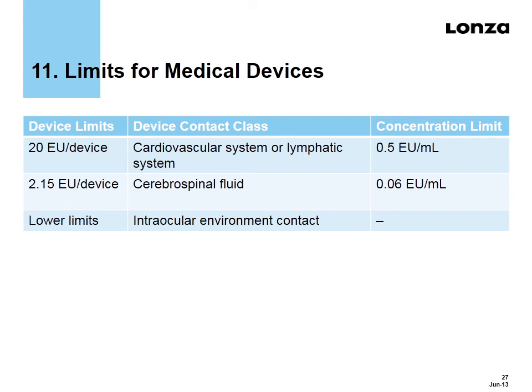Intraocular devices is a new category stemming from the use of solutions which were not originally meant for use internally during eye surgery, which caused problems attributed to endotoxin contamination. The new guidance states that a lower limit may apply, but the firm could contact the appropriate review division for specific recommendations.